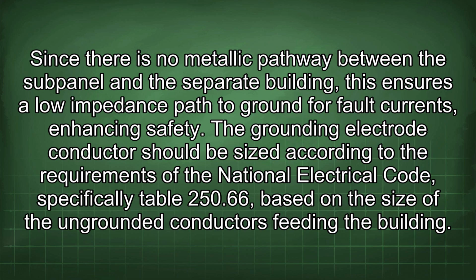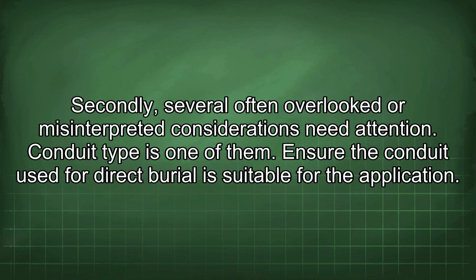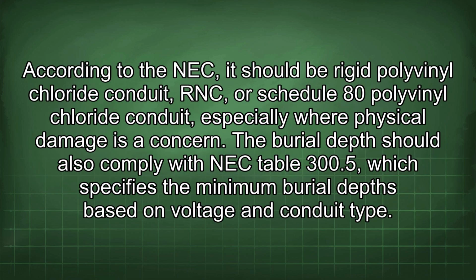The grounding electrode conductor should be sized according to the requirements of the National Electrical Code, specifically Table 250.66, based on the size of the ungrounded conductors feeding the building. Secondly, several often overlooked or misinterpreted considerations need attention. Conduit type is one of them. Ensure the conduit used for direct burial is suitable for the application. According to the NEC, it should be rigid polyvinyl chloride conduit, RNC, or Schedule 80 polyvinyl chloride conduit, especially where physical damage is a concern.